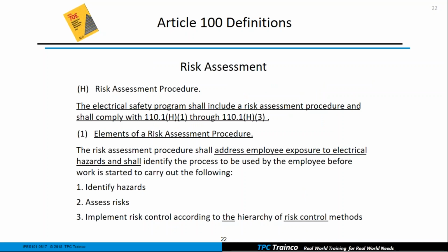So it tells us that our electrical safety program shall include a risk assessment procedure, and it has to comply with H1 through H3. So we have to have a way that we can accomplish this. And I like to put it all in one form. If I can do a job briefing, if I can do shock hazard analysis, and then do my risk assessment all in one form, that's just the best way to do it, I do believe. But the elements of my risk assessment procedure have to address the employee exposure to electrical hazards. They have to identify the process.